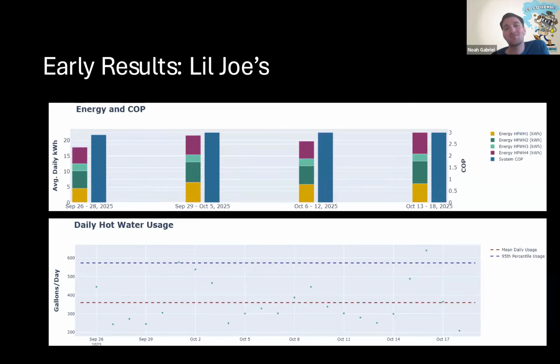Last but not least, we have Lil Joe's restaurant. Quite good performance here, around 3 COP. They do have a little lower daily water use with some outliers, so a bit of an easier load on that system. Also some really good temperature conditions so far. This is in a warm climate, and we've only been monitoring during the summer, so the beginning temperature is about 60 to 100 degrees outside. That's really optimal for performance there. Like we were showing previously, high temperatures are going to be good.